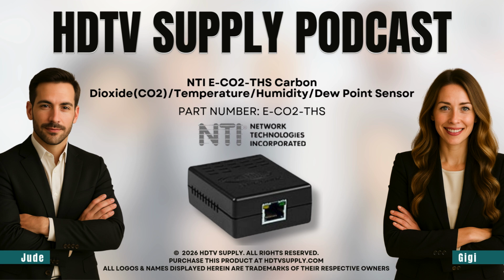Now looking at the physical side, it's an RJ45 connector, so it just plugs in with a standard Cat5 or Cat6 cable. Which is great for easy integration, but the really smart part is how it communicates. It uses RS-485, and that's a digital signal. In a server room, that is everything. Those places are incredibly noisy, electrically speaking. All the power supplies, the UPS units. If you tried to run an analog signal through that electrical chaos, the interference would just scramble the data, you'd get ghost readings. But because this is digital, it has a high resistance to all that electromagnetic noise, the data stays clean.